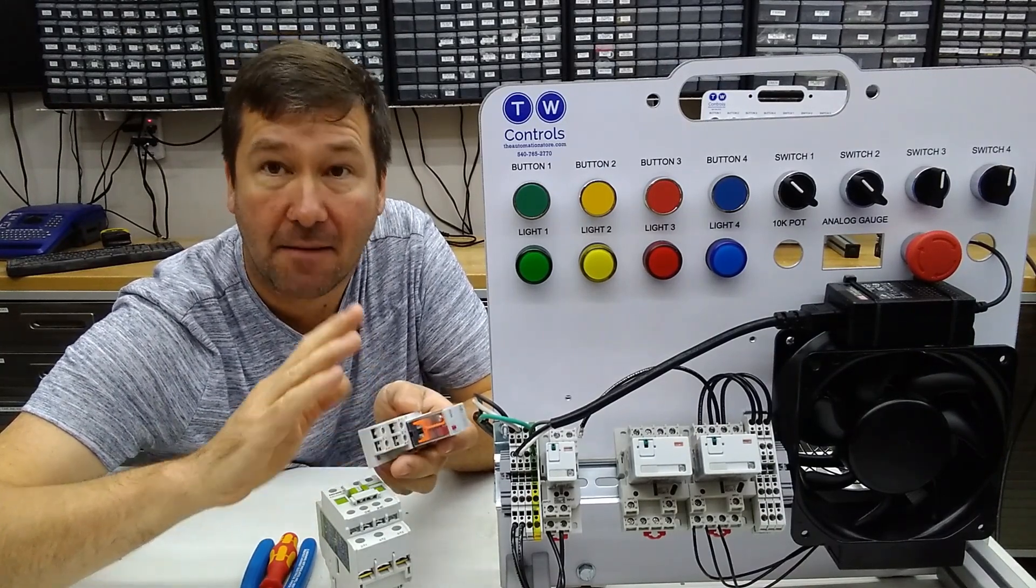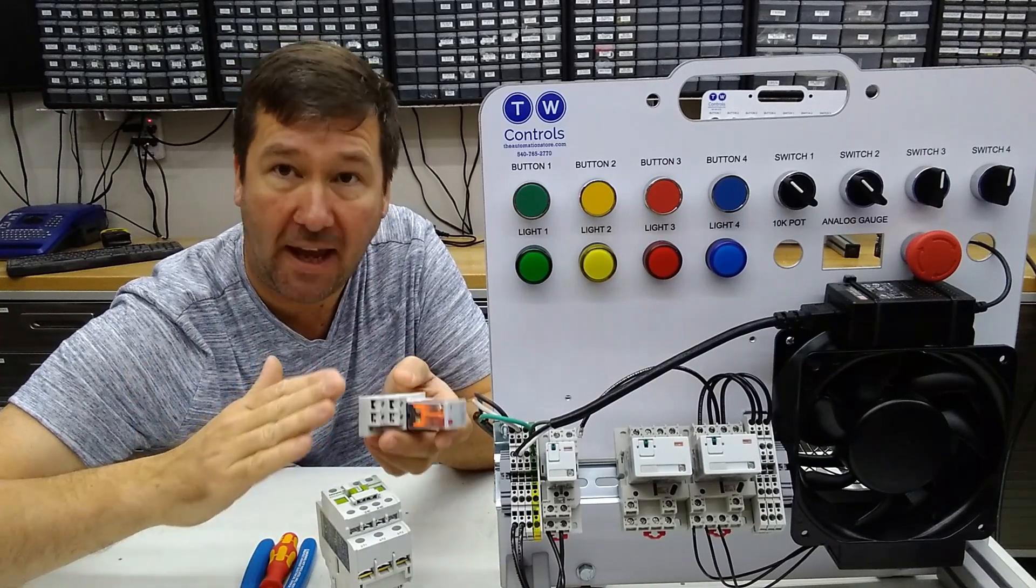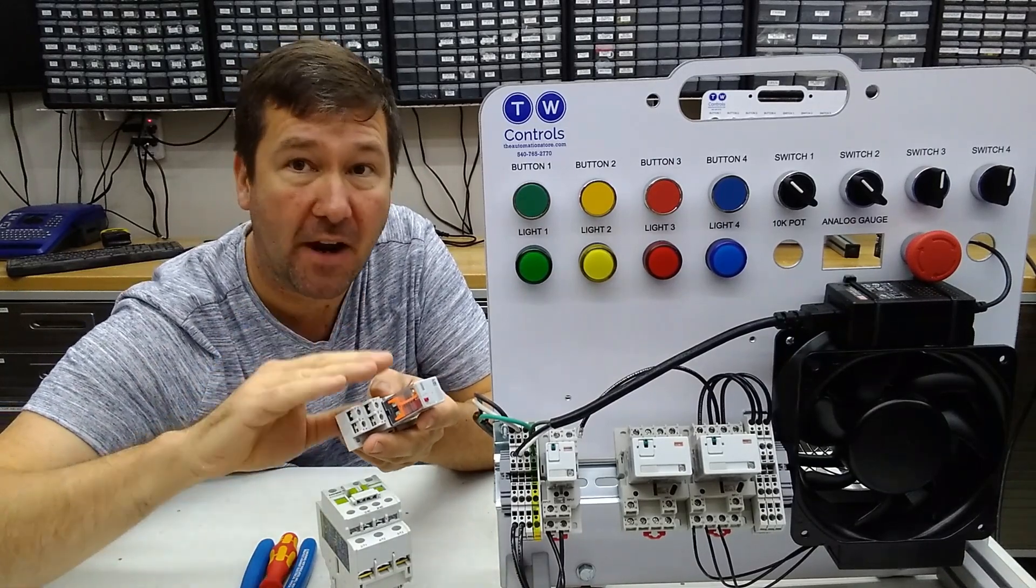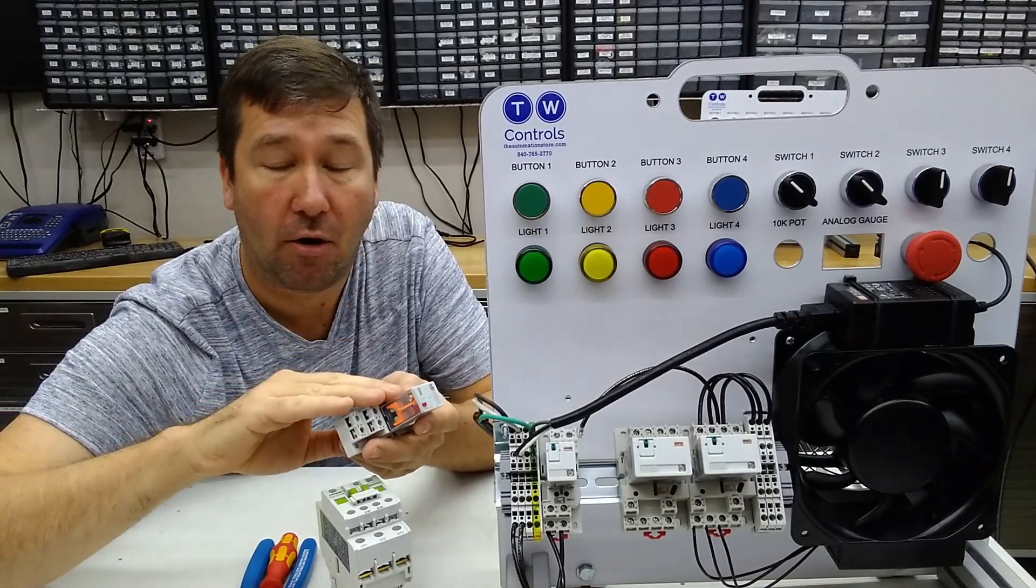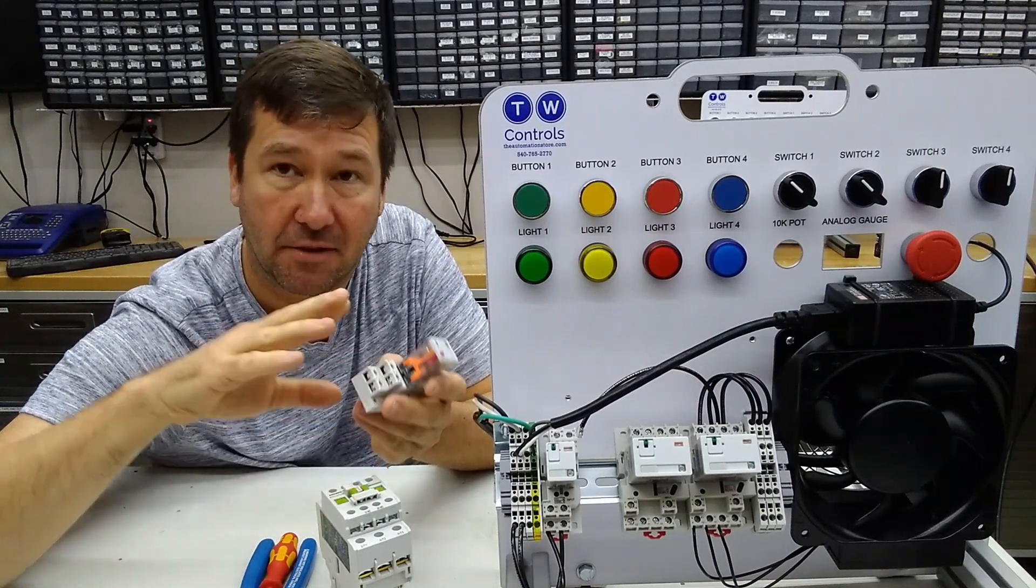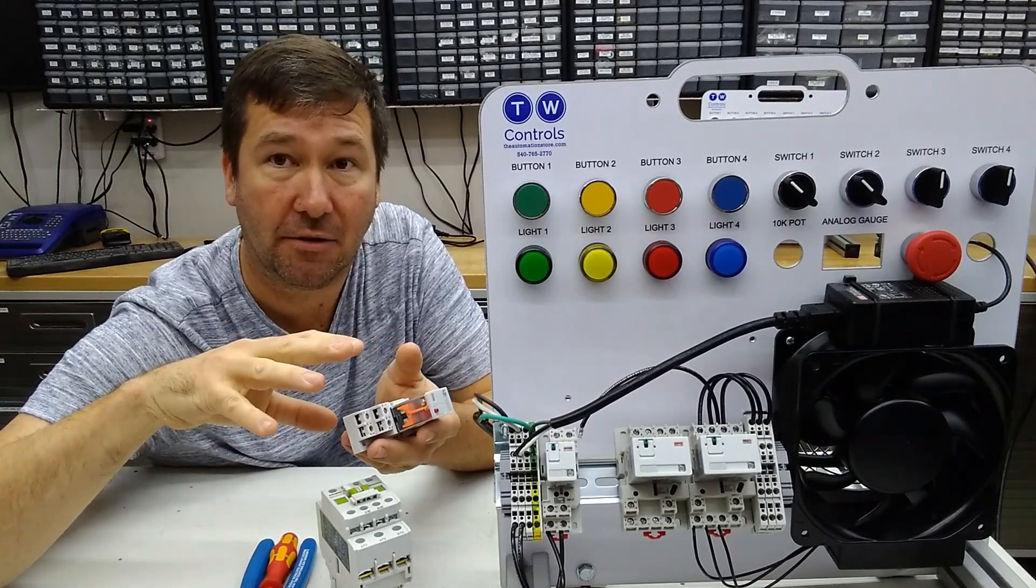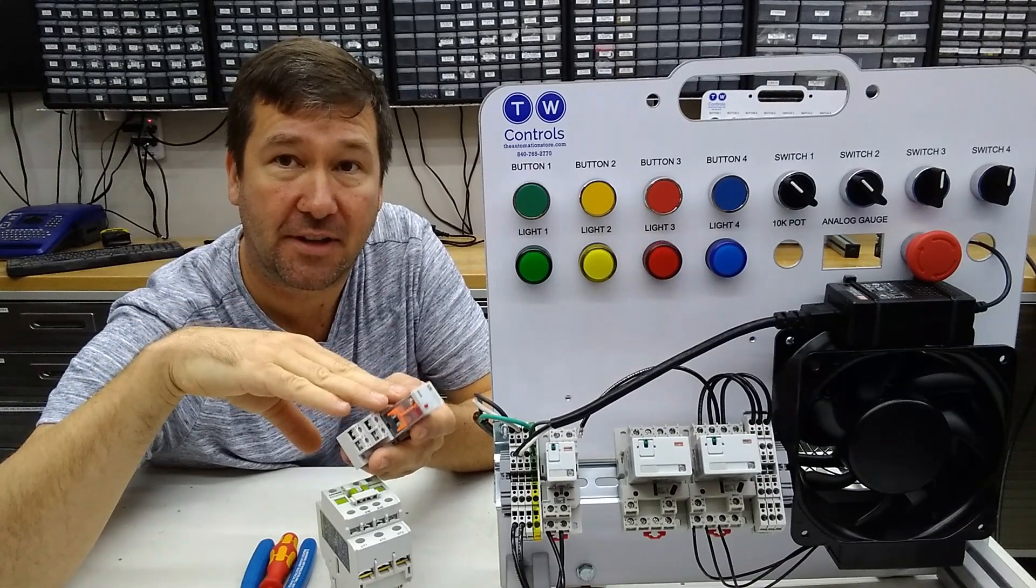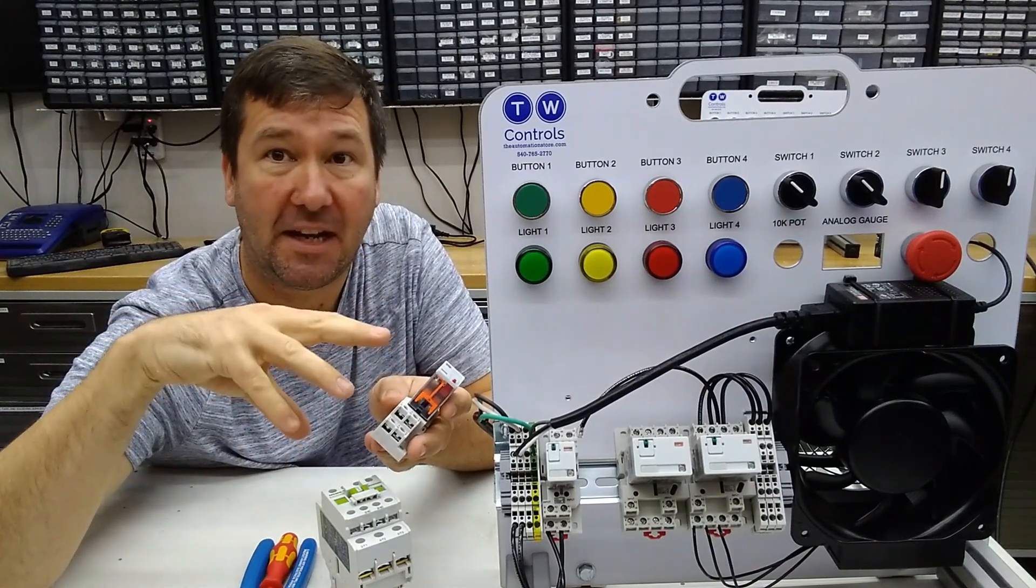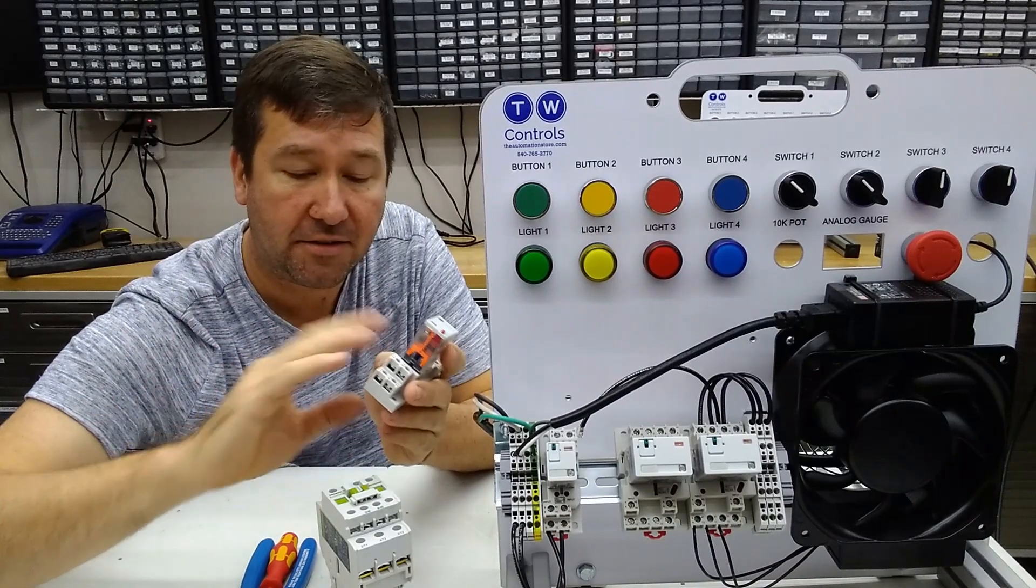That's a big drop when you go from AC to DC, and that'll be very common on relays and contactors. So if you have a DC load, you need to make sure that your contactor or relay can handle that many amps on DC.